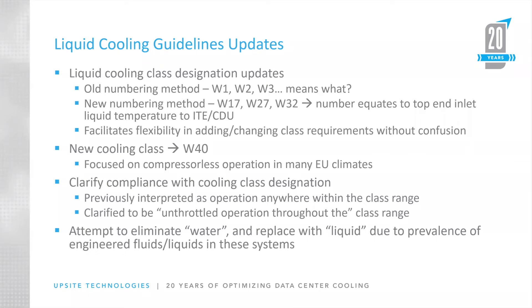That brings the definition in line with the air-cooled side — air-cooled equipment designated for the A2 cooling class can operate unthrottled through the entire temperature range. We didn't have that consistency within the W class designations, but we do now. There's also been a deliberate attempt to eliminate the word 'water' and replace it with 'liquid' — not because people are scared of water, but because we're finding more scenarios involving engineered fluids in these systems.